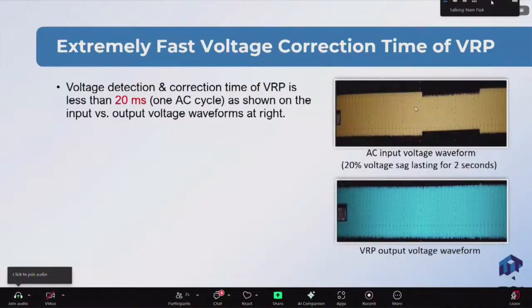When this can happen, if somebody, your neighbor, or you have a huge machine that pulls hundreds and thousands of amps, maybe, get started, and the transformer goes into some saturation mode, and you have a 20%, 30% voltage drop for a fraction of a second, maybe 1 second, something like that. So we simulated that kind of worst-case scenario, fast voltage change.